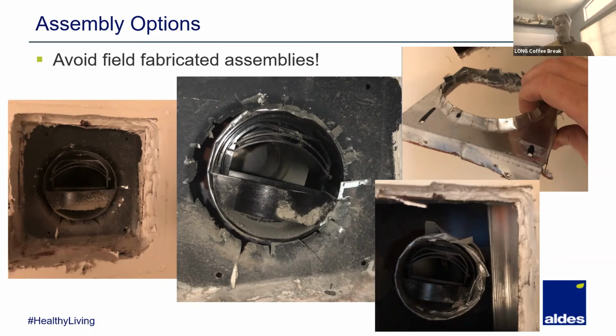But we talked a little bit about hotels. That is a perfect example of where we want to try and maintain that pressurization. And we've all been in that hotel that has suffered from the lack of outdoor air and some of the issues and problems that you can smell or see as soon as you walk into the place. Absolutely. Especially in a cold climate where you have an indoor pool. If you can smell the pool in the hallway or in your room, that just means that there's a pressurization issue. Too much exhaust, not enough supply, and balancing those systems with something like the airflow regulator is one easy way to make sure that you maintain positive pressurization when you're in close proximity to something like an indoor pool.